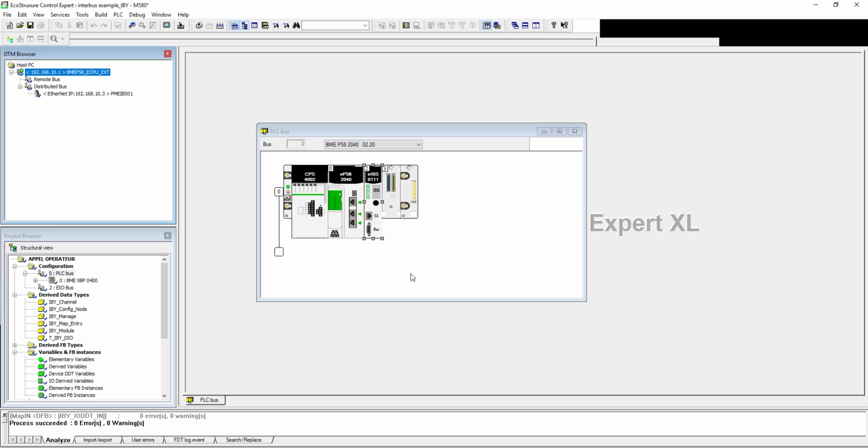And now one other thing we want to do, because in terms of the configuration, and this is really important, the PMEIBS doesn't really rely on external software for its configuration. The utilities help modernize what you had before on the Premium platform, but the configuration is actually stored as part of the Unity project or Control Expert project, and the way it does it is using faulty device replacement, or fast device replacement, FDR, on the CPU.